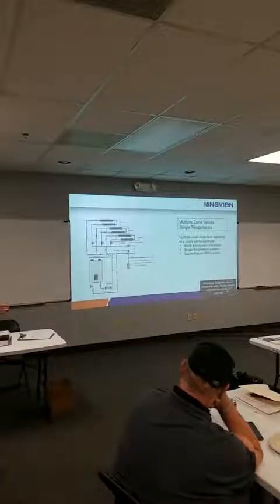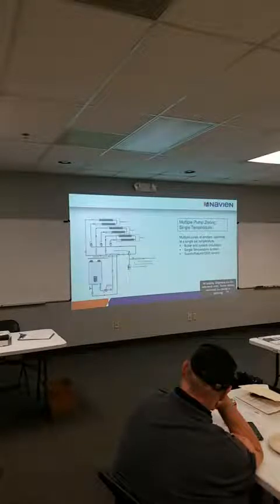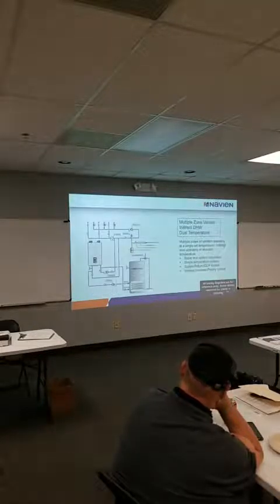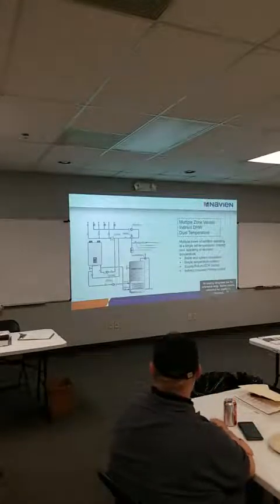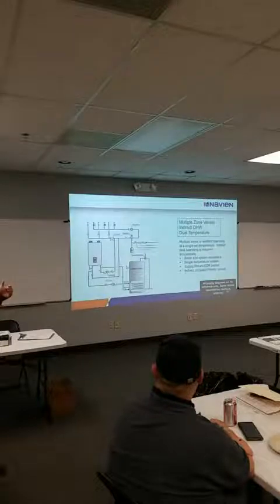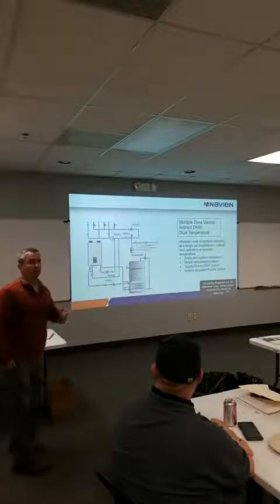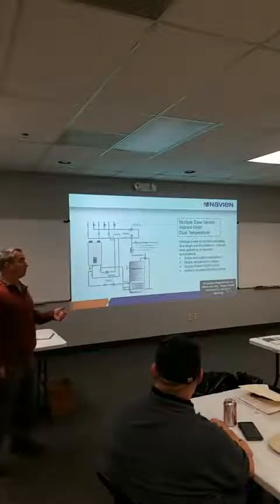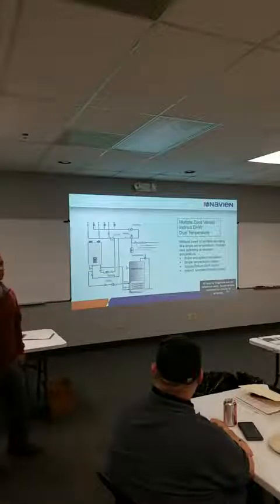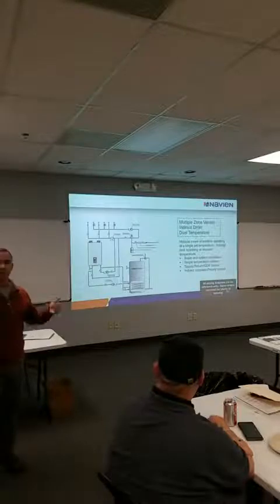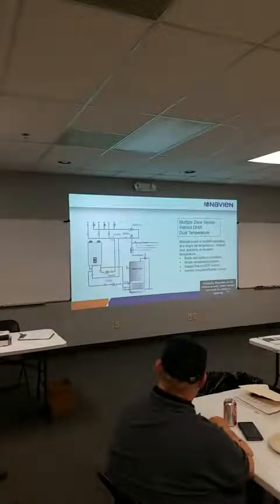So same piping diagrams, nothing crazy here. They look the same as the NHP, we're not doing anything different here. So again, if you're doing domestic hot water, you can pipe it in, we can power that pump, you can run your tank mounted aquastat back, and you can give that tank priority and temperature difference if you want. You can run those pumps at the same time, at the same temperature, or you give it a higher temperature and give it priority if you want.